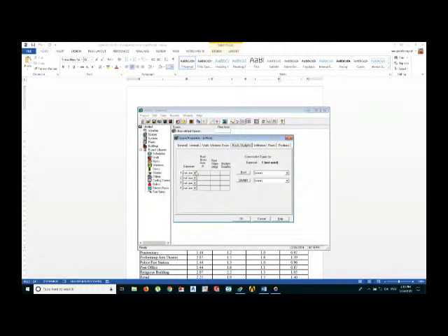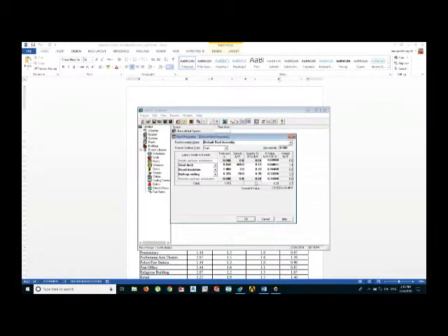And third one is the roof skylight. My roof is horizontal, so I will select H, which is 100 square feet. If your roof is inclined toward north or east, it is an inclined roof, you can define these parameters here. And you will define also the roof assembly. My roof is made up of 8-inch common brick, and there is no insulation, 1-inch stucco, and built up roofing. So just press OK. These are the materials of the roof. So you define the R value. If material is not present here, you can just put the name and put its R value manually from ASHRAE.